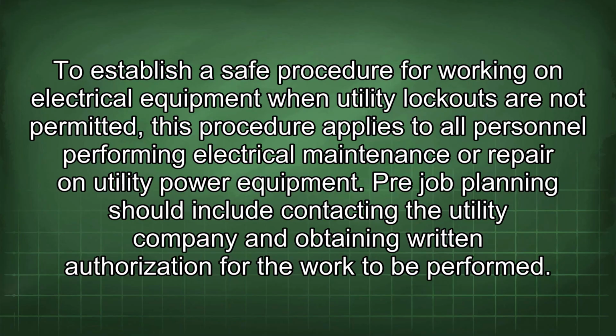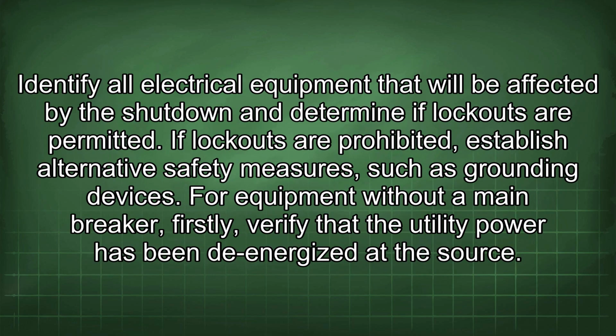To establish a safe procedure for working on electrical equipment when utility lockouts are not permitted, this procedure applies to all personnel performing electrical maintenance or repair on utility power equipment. Pre-job planning should include contacting the utility company and obtaining written authorization for the work to be performed. Identify all electrical equipment that will be affected by the shutdown and determine if lockouts are permitted. If lockouts are prohibited, establish alternative safety measures, such as grounding devices.